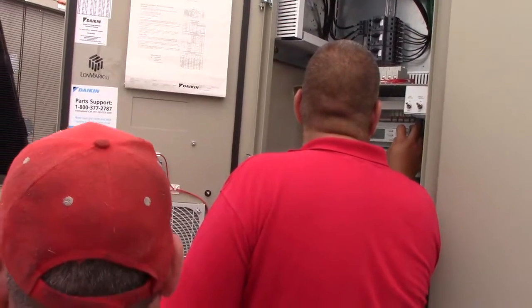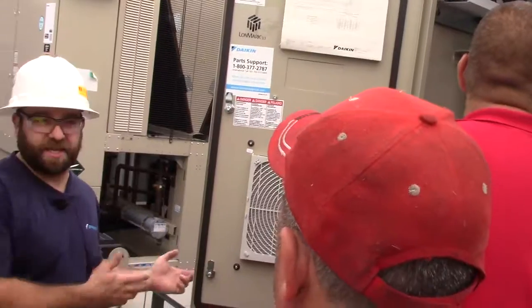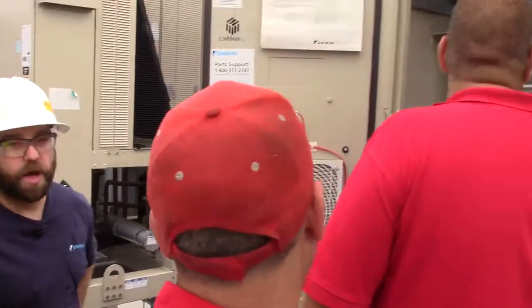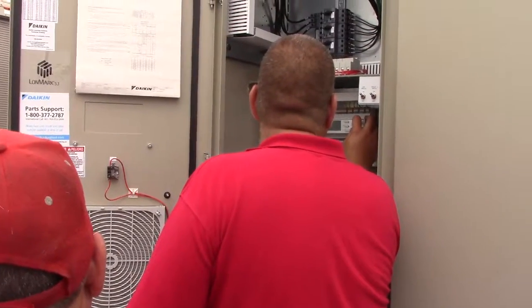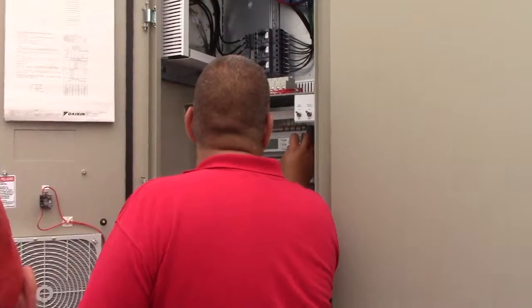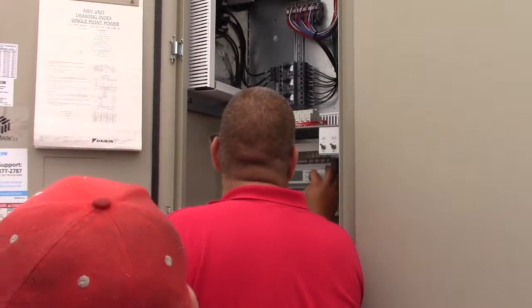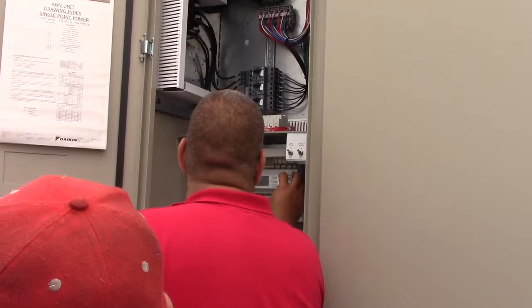So it's off a standard VFD like you would have on a blower. In theory the drive goes AC to DC back to AC again, is what I'm told. But the motors are technically AC motors, rated to do the higher frequencies. Depending on the application, and without looking at your submittal I don't exactly know your total ranges, it could be as high as 86 hertz on the high end, and as low, like I said, as 12, 14. Just depends on the application.